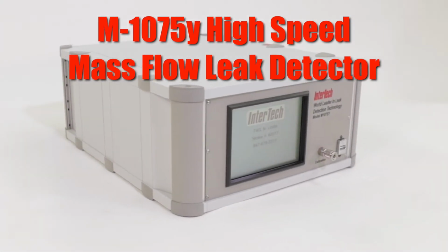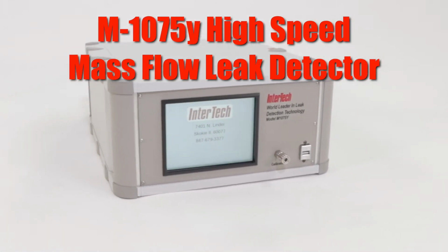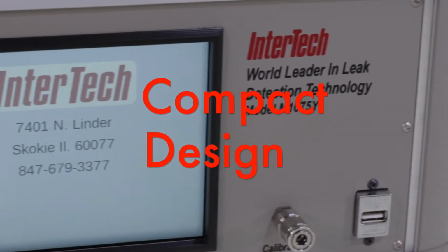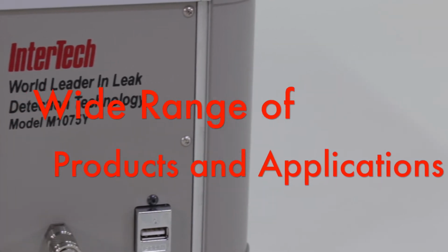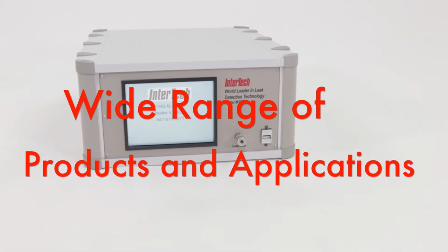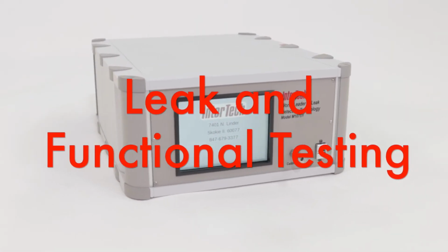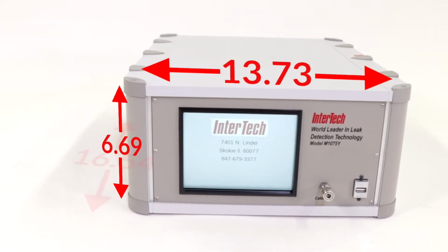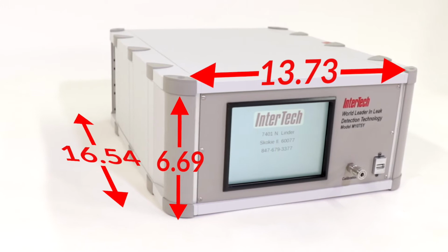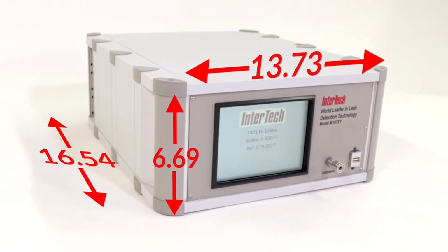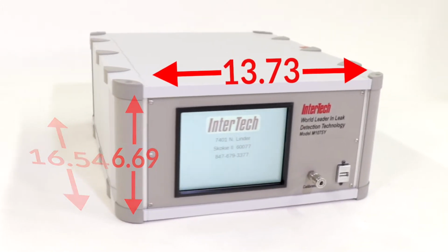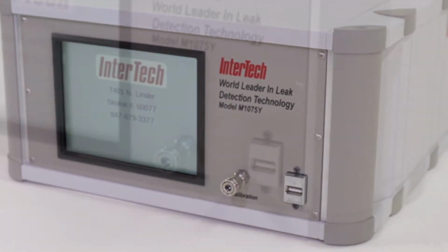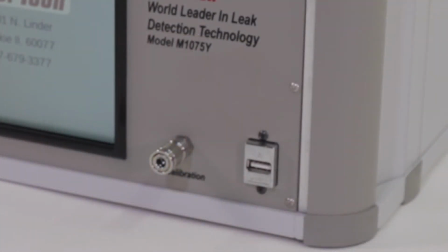The M1075 high-speed mass flow leak detector, built by InterTech Development Company, offers lab-quality high-resolution leak rate measurement at the fastest production test cycle times possible. This 21st century compact technology functions on the lab bench as well as in high-speed production systems, with standard features including storing 99 individual part programs on board and infinite programs storable via the USB port.